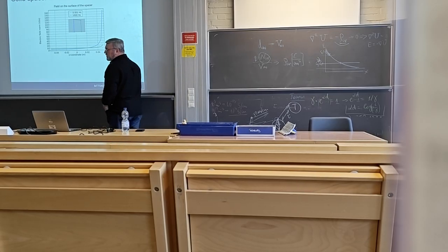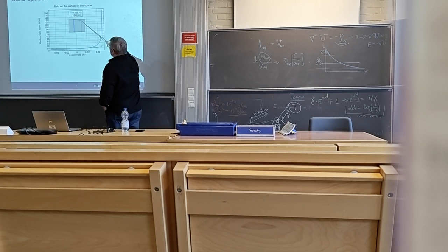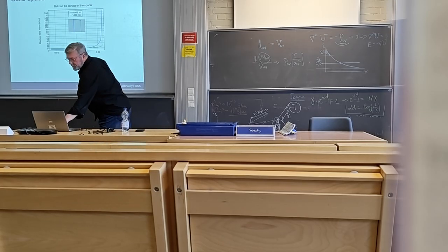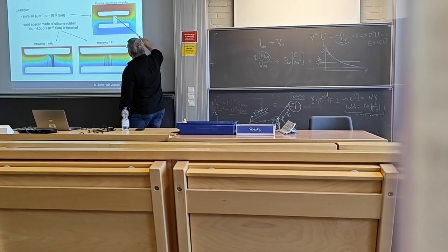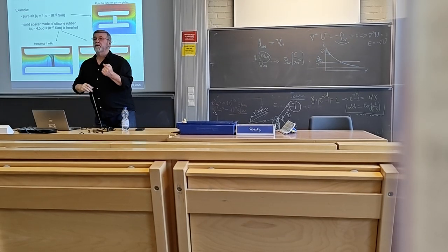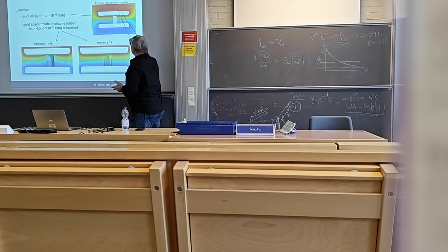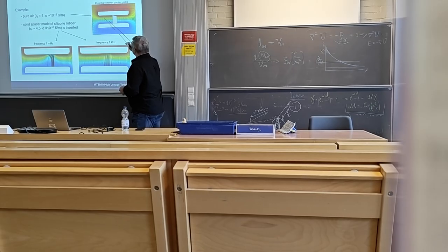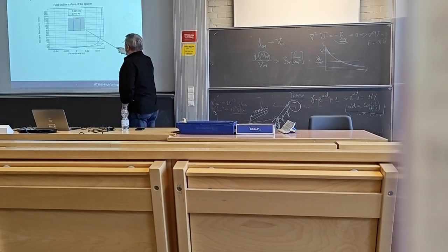Oh, sorry, not that one, just along the central one. This is even more complicated because of this one, but if you just take a straight line, what will happen? Just here, like this. Here we have a triple junction, right? You have a contact point of three materials: this one, metallic, in terms of potential, air, and this silicone rubber. So if you just look at the field here, that's what we will observe.